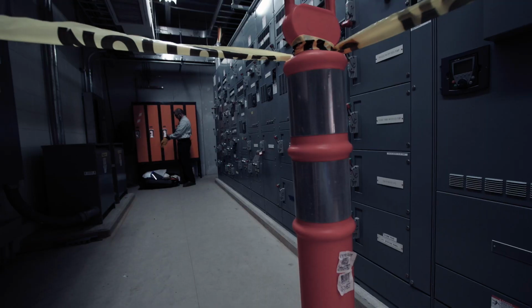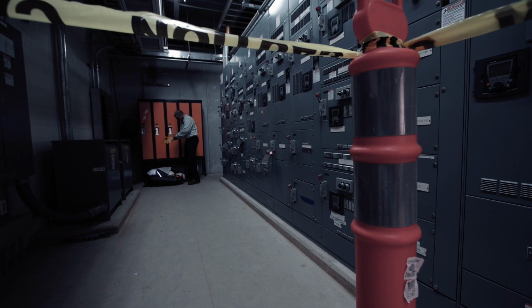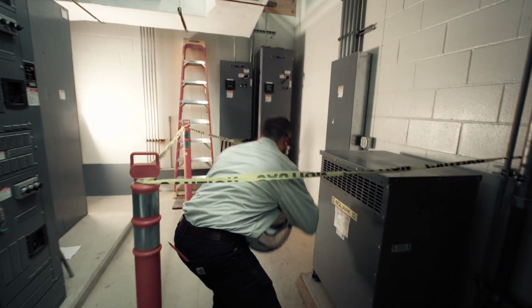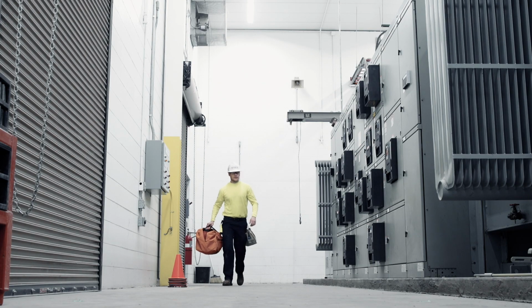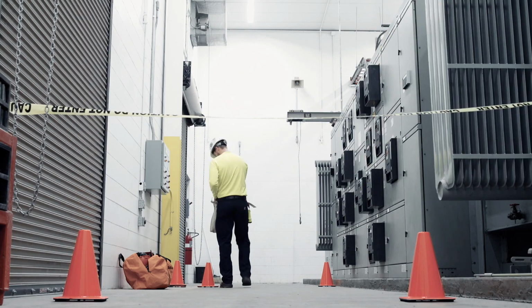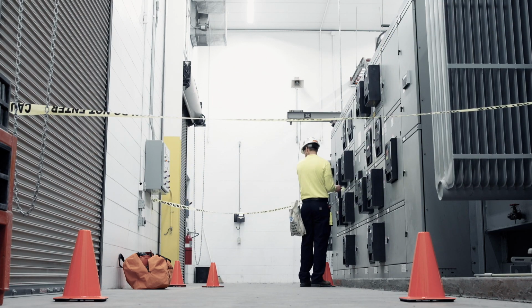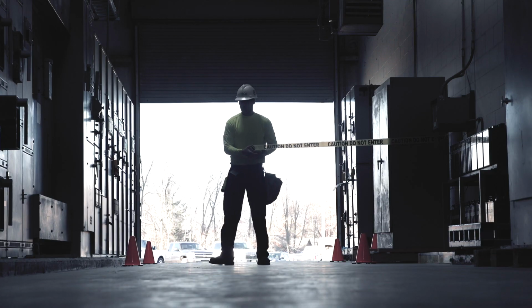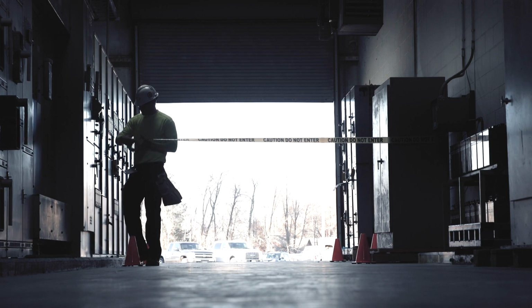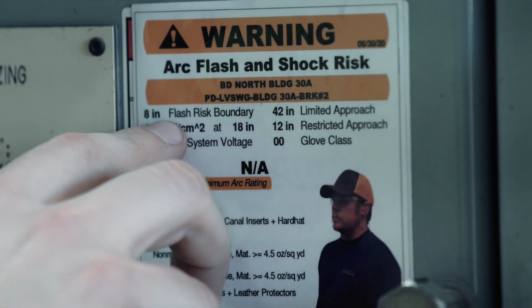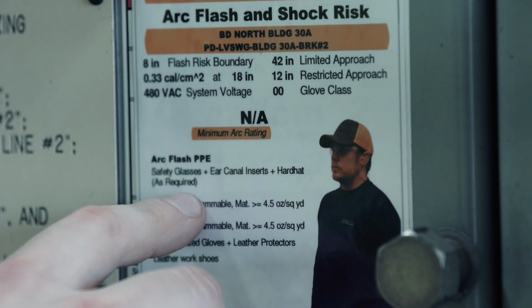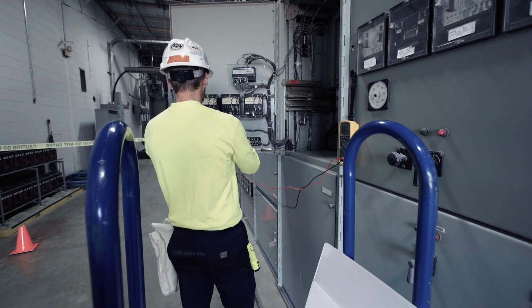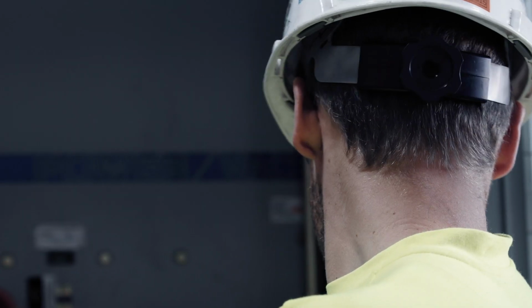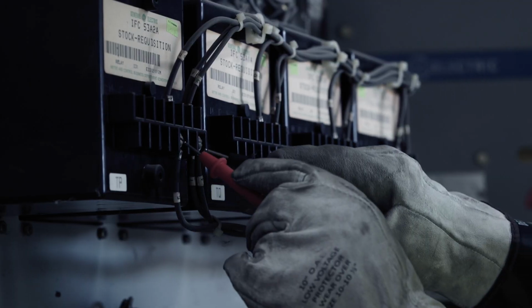When you're setting up barricades, remember that the arc flash boundary is independent of the approach boundaries. Make sure your barricades meet or exceed the greatest distance listed between the arc flash and the limited approach boundaries. What counts as a barricade? A physical obstruction, such as tapes, cones, or A-frame type wood or metal structures intended to provide a warning and to limit access. Be sure to use barricades whenever an electrical hazard exists in order to warn and restrict accidental contact of unqualified and qualified individuals.